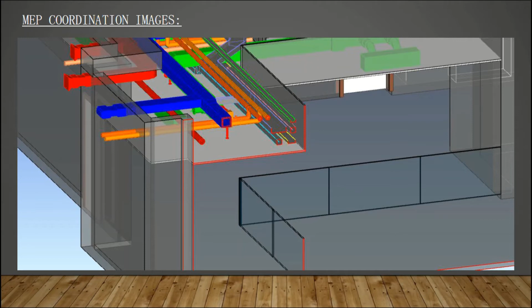The cable trays and ladder should be placed in such a way that the cabling is easy. The spacing should be adequate for the cable rollers. These rollers are available in different sizes. The number of cable layers over the tray should also be taken into account. The trays and trunking that are susceptible to maintenance and upgrade should be placed in the bottom layers.